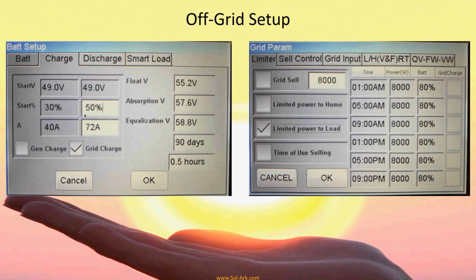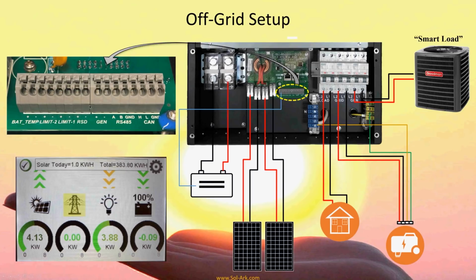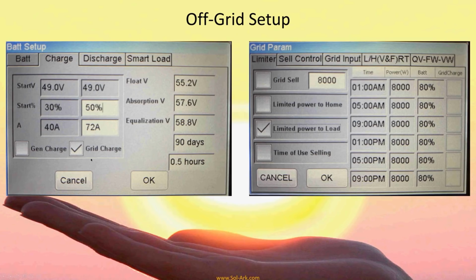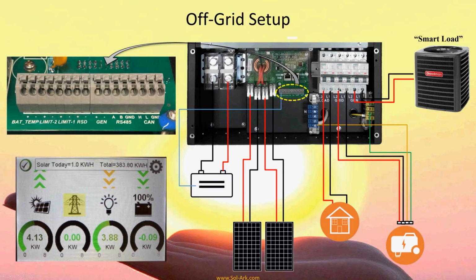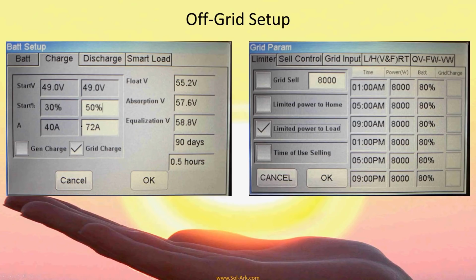Okay, so if we're setting this up for off-grid, we need to very carefully set this start percentage or start voltage, because that is when it's going to turn on this gen start relay. Again, because our generator is hooked into the grid breaker, we're going to actually use grid charging, not generator charging.